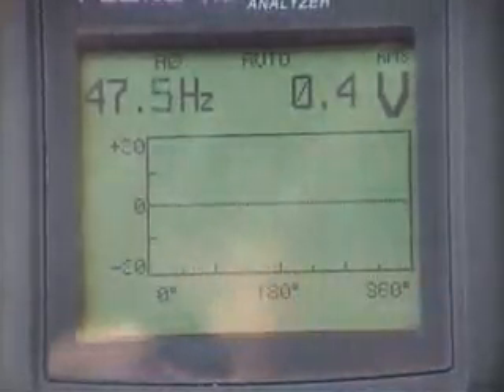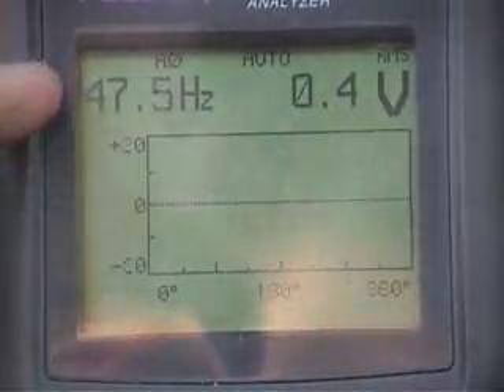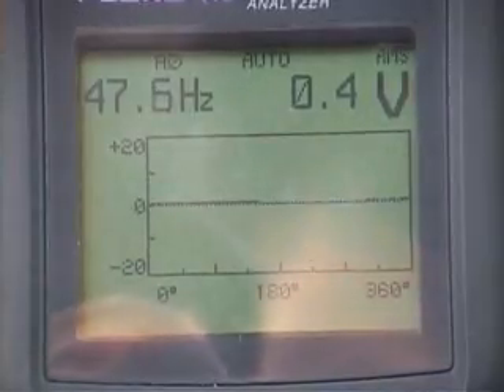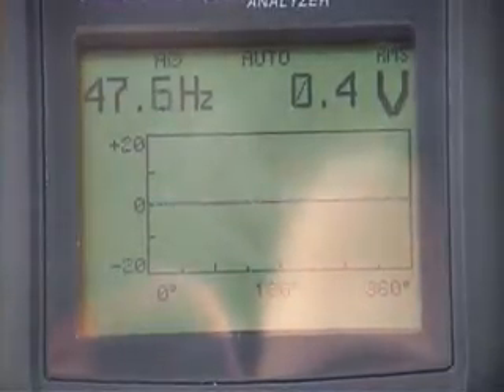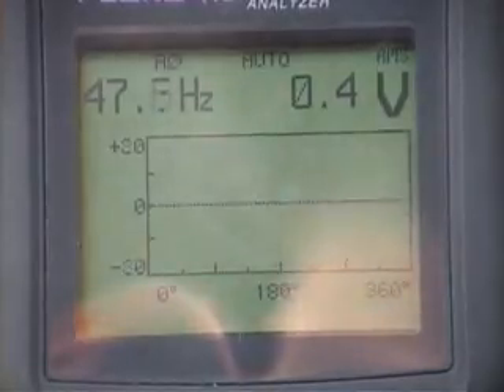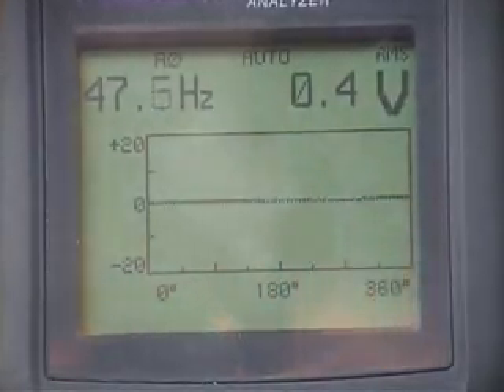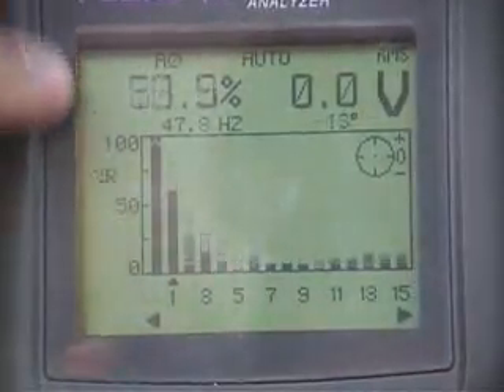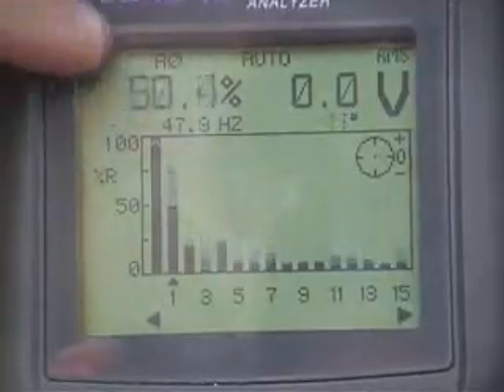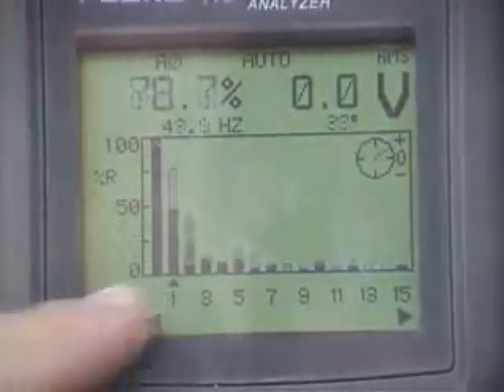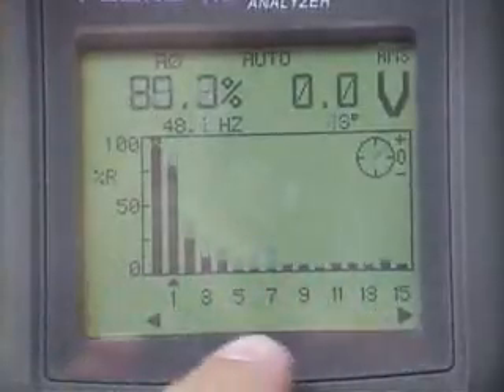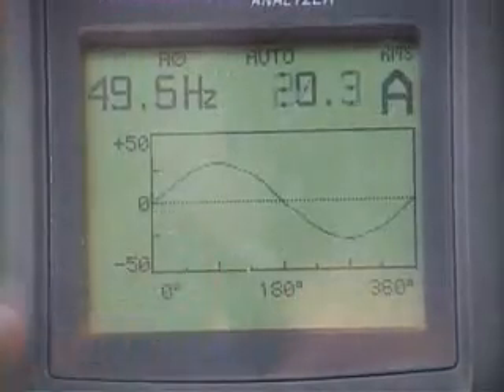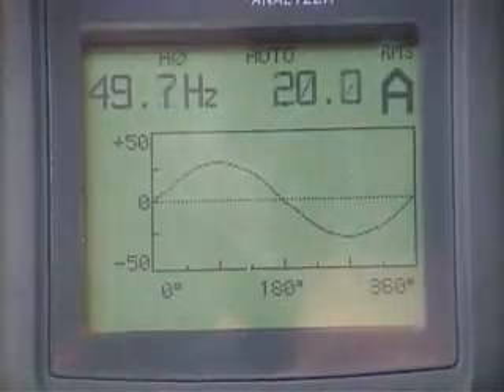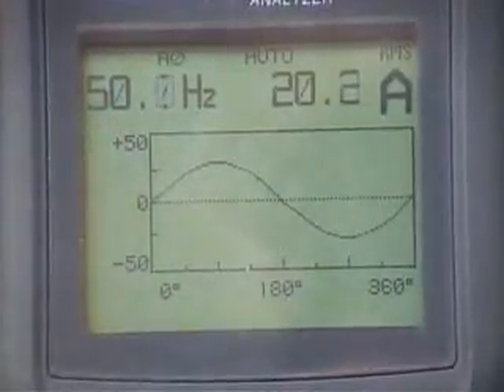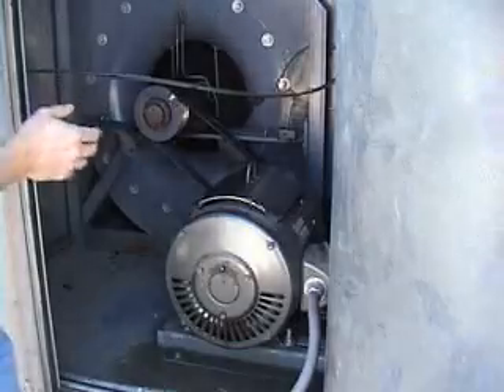Right now the frequency drive is operating and we're putting out 47.4 hertz to the fan. So we're not at 60 hertz, where we would be running at 460 volts and the 32 amps we were looking for. So right now it's adjusting those things. If we look at what the frequency looks like, you can see our fundamental frequency right here, and we're running between 70 and 80% of our fundamental frequency. You see I have a lot of noise, extra frequency harmonics back in here. Here we can see what our sine wave looks like. Here you can see we're up now to 50 hertz, running at 20 amps. This is the supply fan.